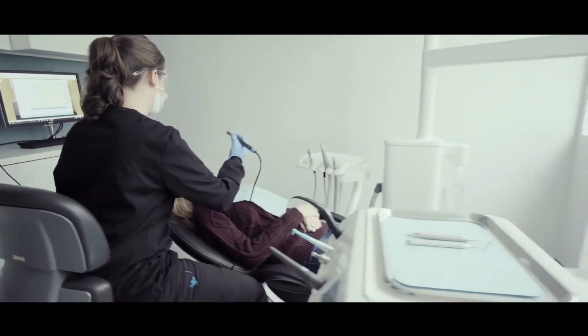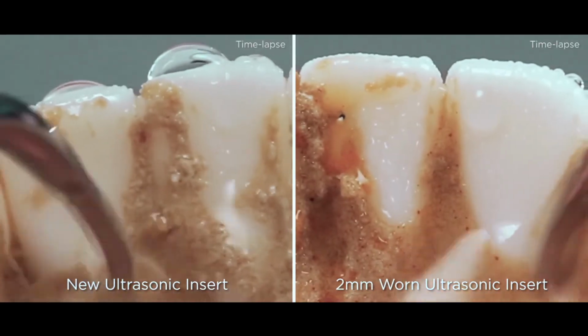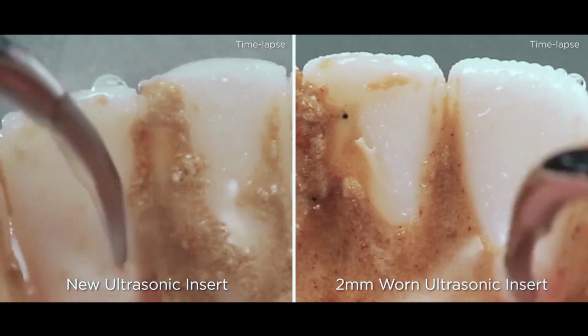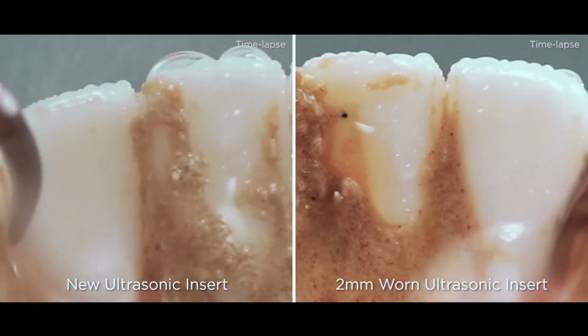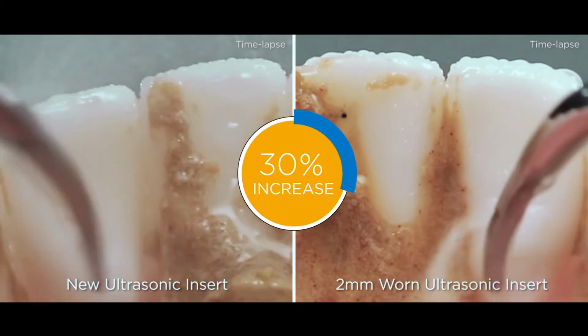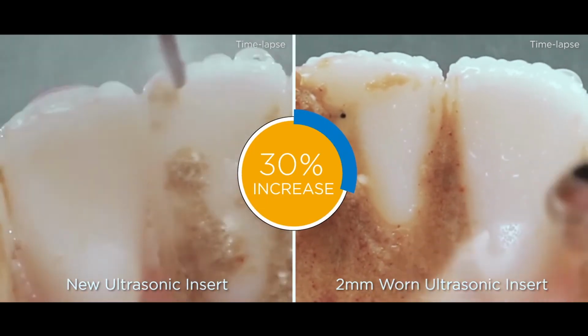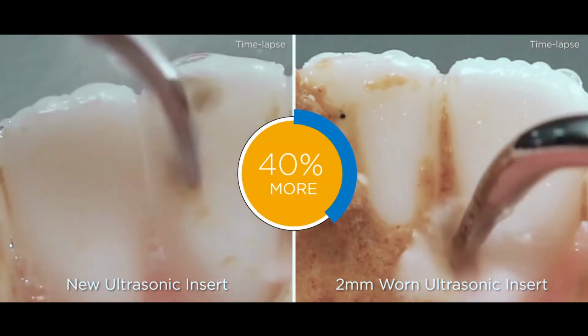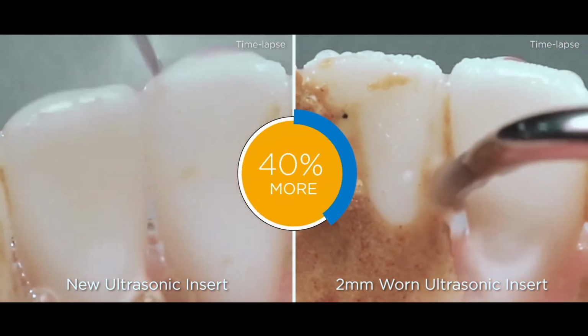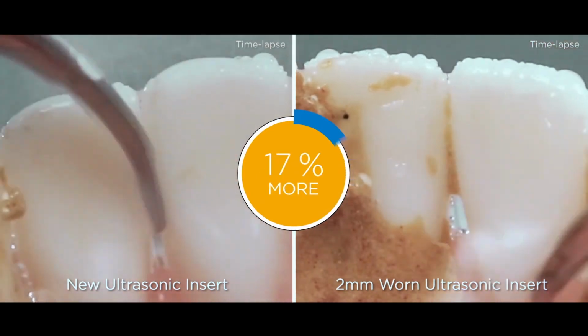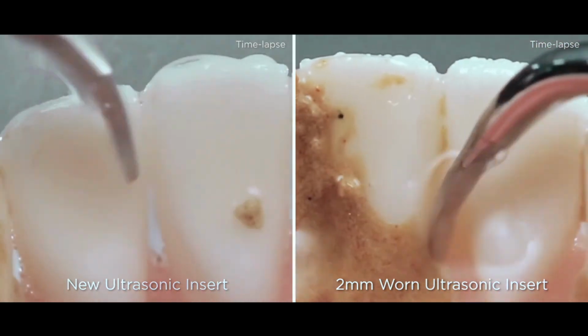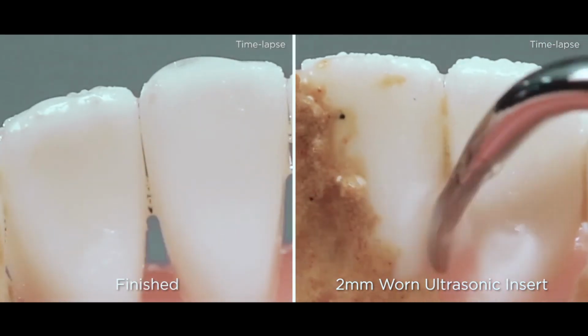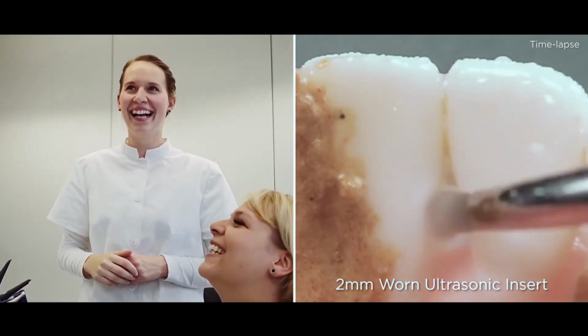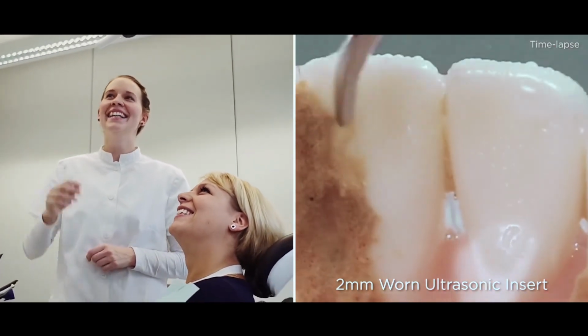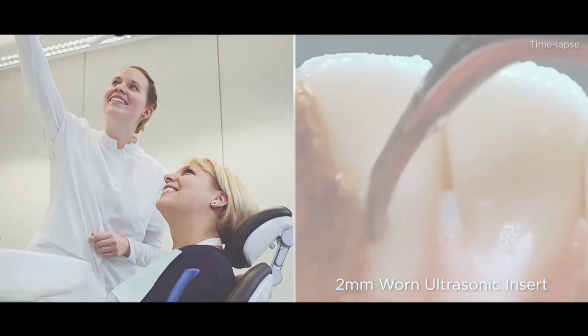In this test, we compared a new Cavitron ultrasonic insert to a Cavitron ultrasonic insert with only 2 millimeters of wear. On average, the worn insert results in a 30% increase in total scaling time. In addition, a clinician will use 40% more scaling force over the course of the procedure. This may result in an increase in both patient chair time and pressure used by the clinician while scaling. What could you do with 30% more time? Check your inserts regularly to maximize efficiency and comfort for you and your patients.